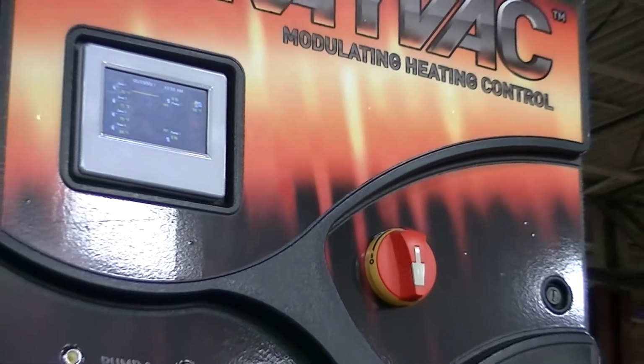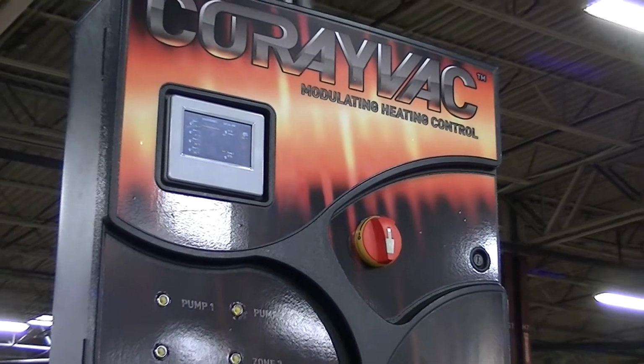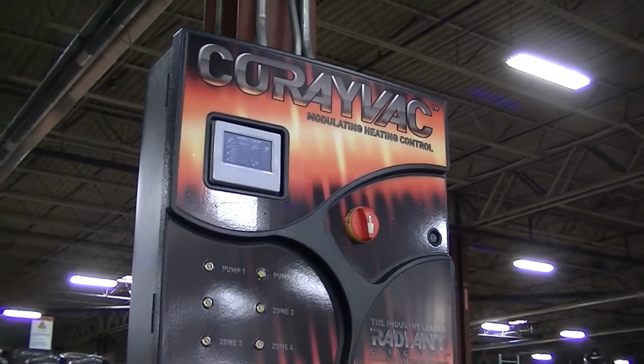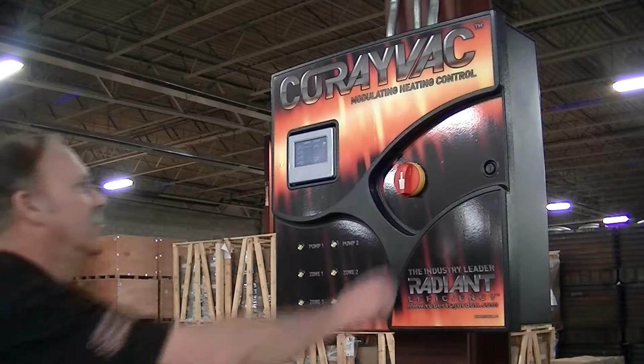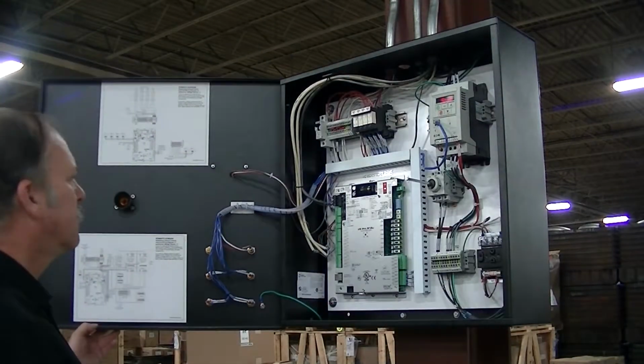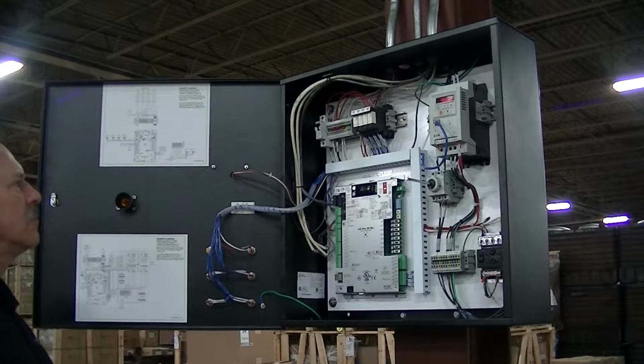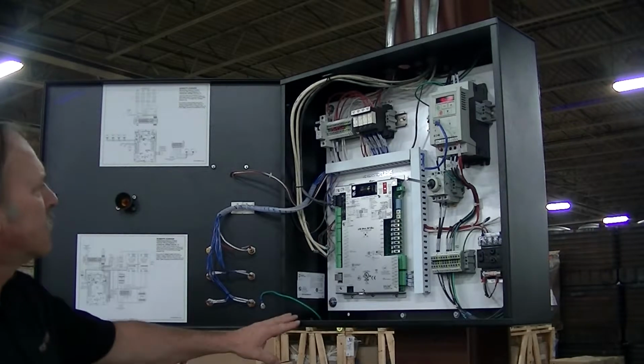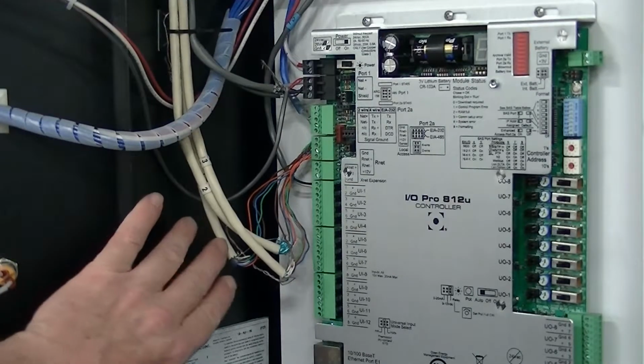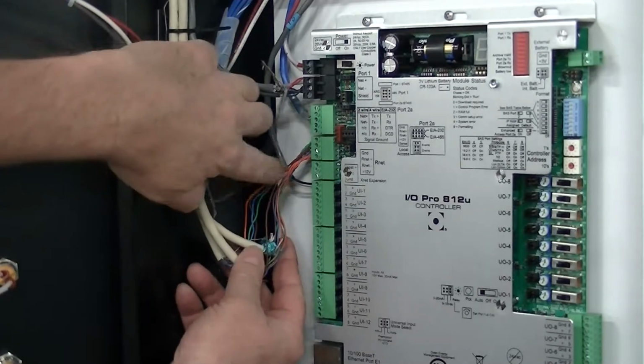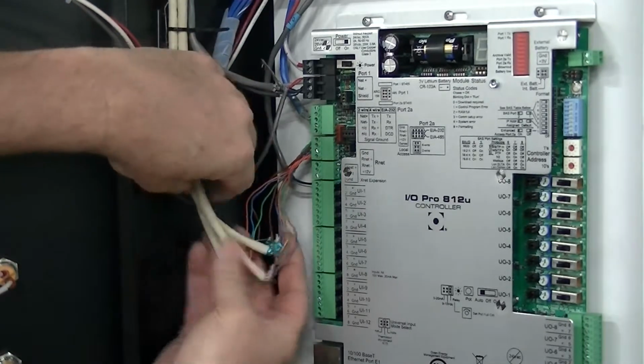Roberts-Gordon offers several types of CoRayVac heating controllers, as well as modulating controls. Today, we will install the CoRayVac Modulating Heating Controller. The first thing to do when opening the control panel is to make sure all wires in the panel are connected to terminals and there are none hanging. Check all wires at the terminals, ensuring that they are secure and will not come off.